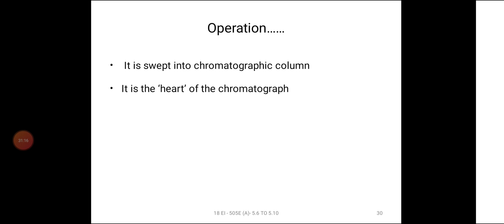The chromatographic column is the heart of the chromatograph. There, the different solutes in the vaporized sample are separated from each other by virtue of their different interactions with the column packing. Due to the column packing, different retardations take place on the sample: polarity, adsorption, absorption, molecular filtration, chemical bonding. Due to all these different retardations, the sample components are segregated into separate zones and bands. They elute from the column exit as different components.